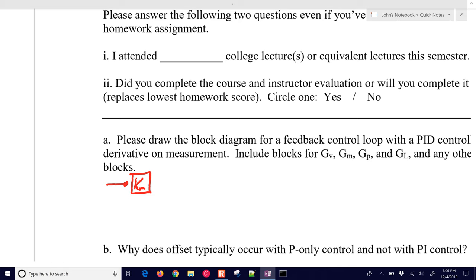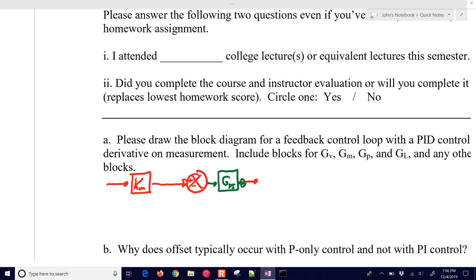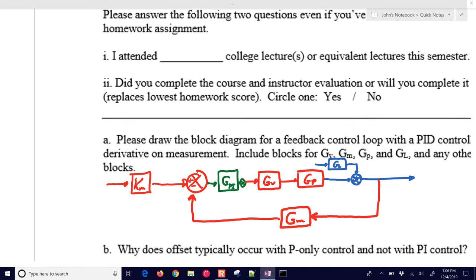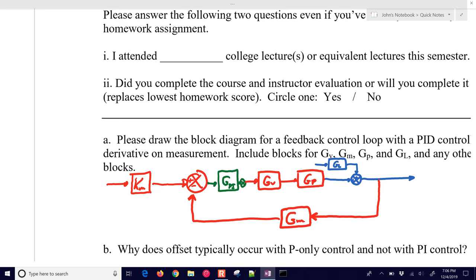We have KM — that's the gain for our measurement. Then we add in the PI controller and the valve, then the process, then the load, and then our measurement coming back. We use GM here instead of KM because GM might include the dynamics of the measurement. Up above, we only use KM because you instantaneously convert the desired setpoint into the measurement signal to compare with the measurement. GM might have an output of milliamps, and we want to convert the setpoint into a milliamp signal, for example.